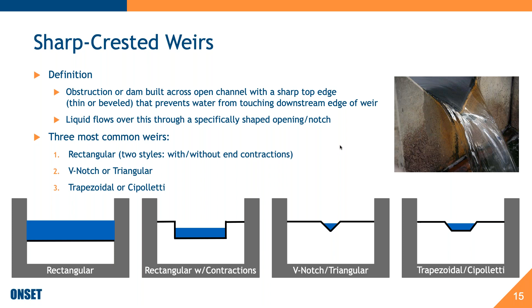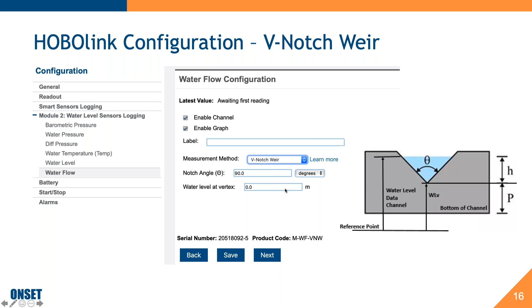So in HOBOlink, now that we have this water flow option, which is pretty awesome, it's also seamless and user-friendly. I'm not the most knowledgeable person when it comes to V-notch weirs, but when setting mine up, it was easy to enter: I have a V-notch weir, here's my notch angle, and here's my water level at the vertex. That's all I had to do, plus tell it degrees or radians. Based on that configured data, HOBOlink provides me with flow—this is flow using a weir, which is really exciting. We also have the option for flumes to be used with our water level sensor for monitoring flow.